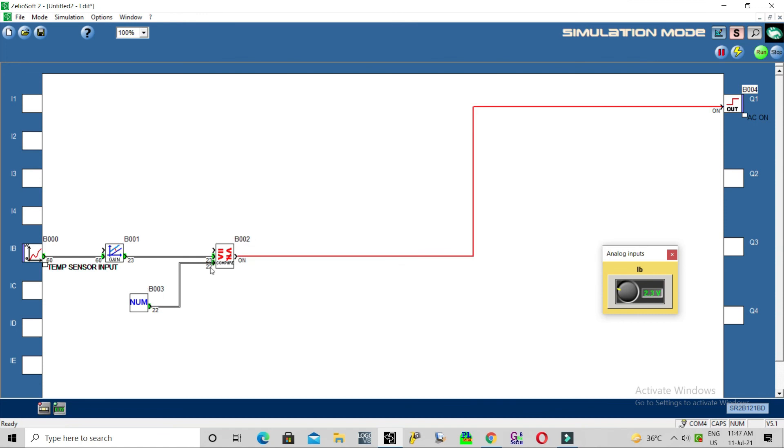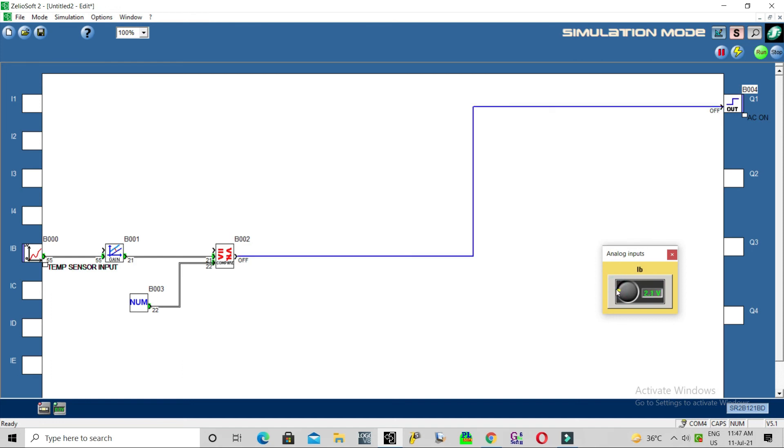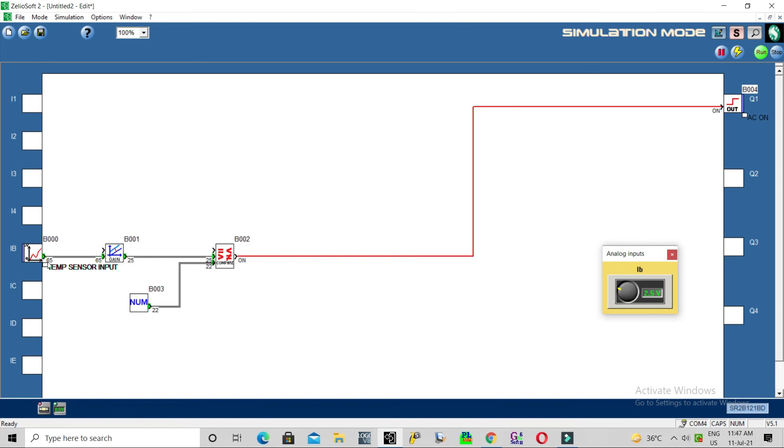When it reaches our set value - now ambient temperature is 23 - so our controller has switched on the AC. Now AC will run and try to reduce the temperature, so obviously temperature will come down. When temperature goes less than our set value, automatically AC is off. Again if it reaches more than our set value it is on. This is how you can scale the analog input value and do your program as per your requirement.